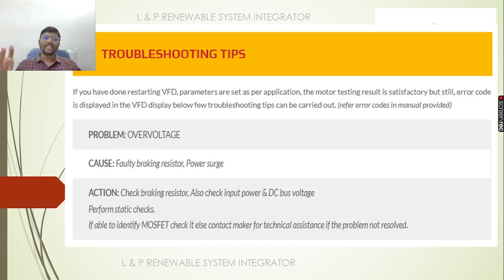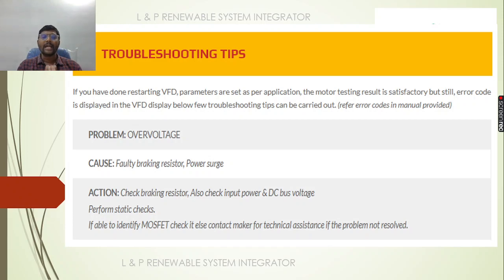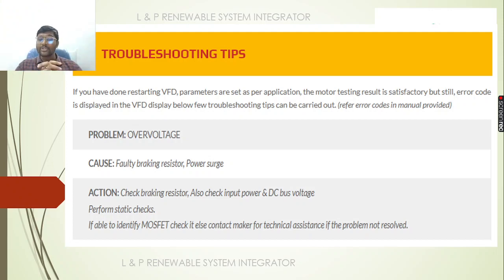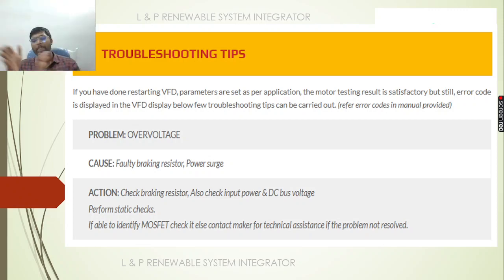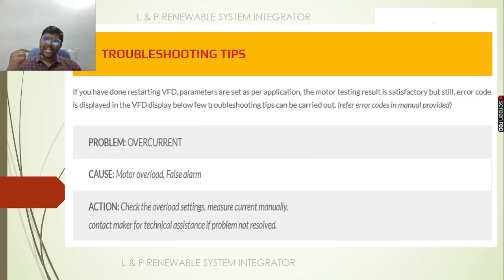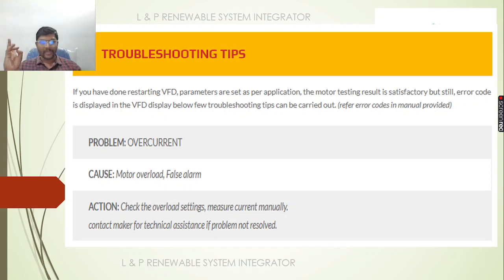Next, if you are facing any overvoltage issue, the cause will be a faulty braking resistor or a power surge. The action is to check the braking resistor, check the input power and DC bus voltage, and perform the static checks. Most importantly, identify the MOSFET and check — contact the manufacturer for technical assistance. Next, if you are facing any overcurrent issue, the cause will be motor overload or a false alarm. Check the overload settings and measure the current manually. If the problem is not yet resolved, contact the relevant technical persons for assistance.